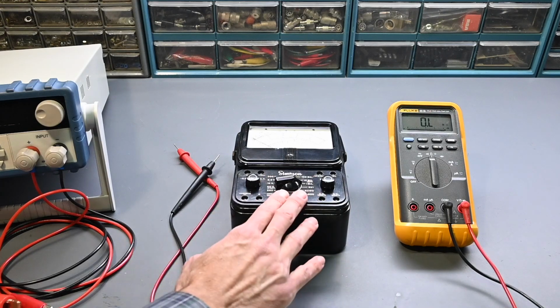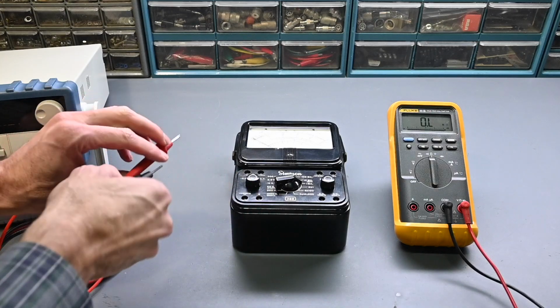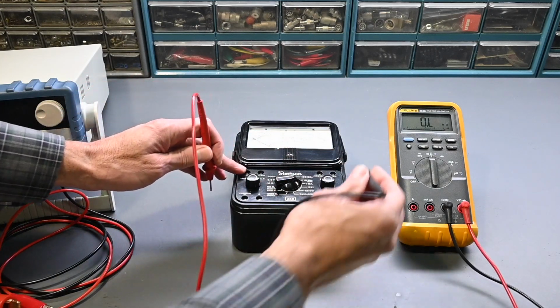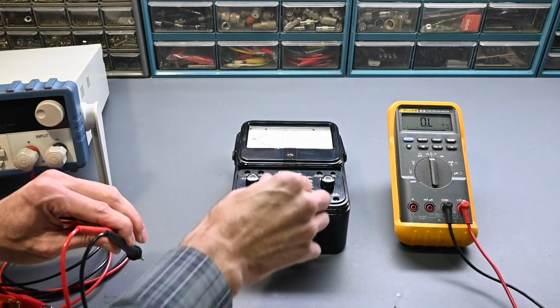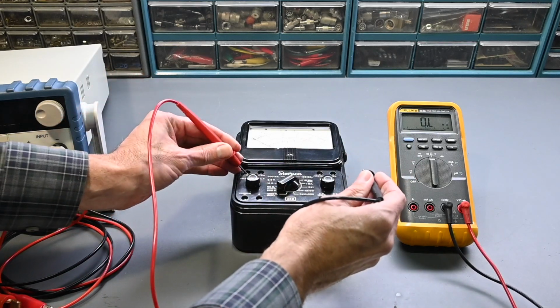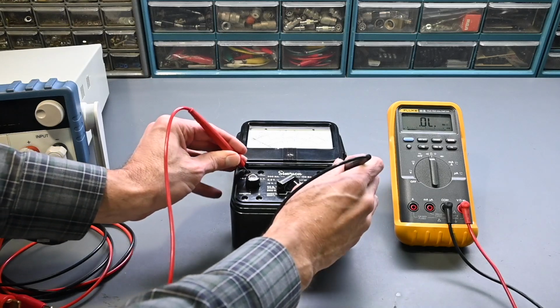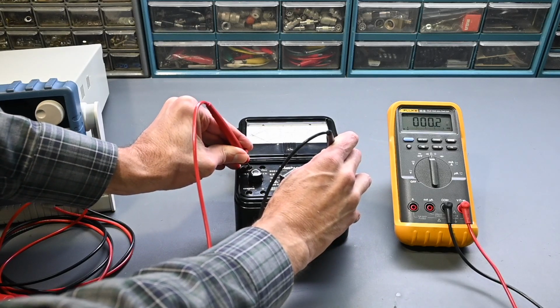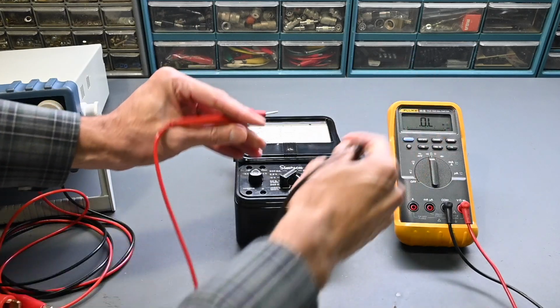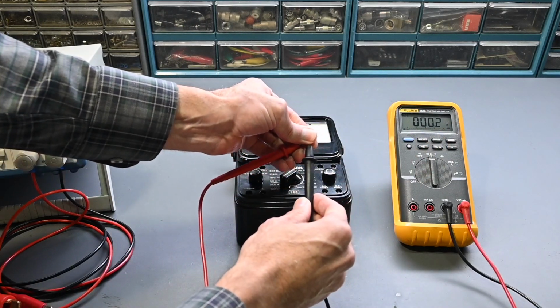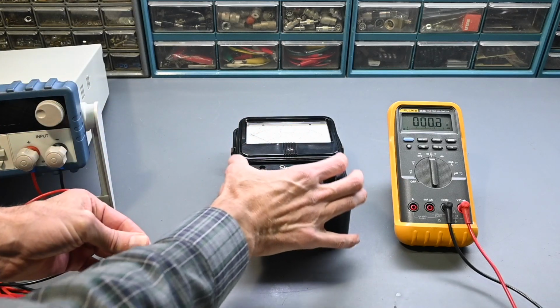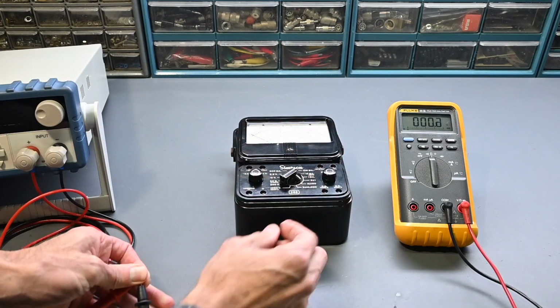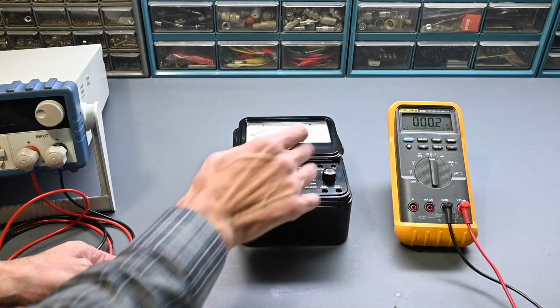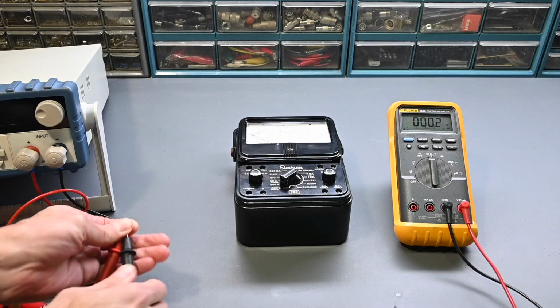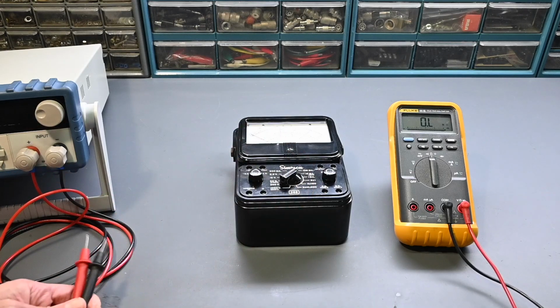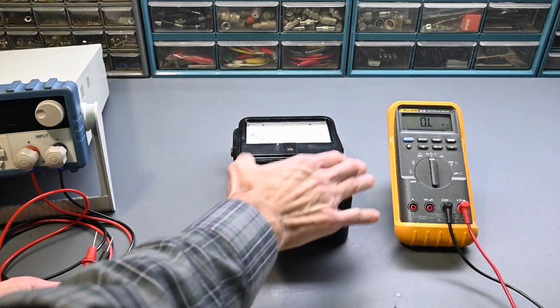And the Simpson 260 does have the ability to measure 10 amps. The 10 amp setting is actually from this jack right here over to this jack right there. I believe it's supposed to be in that position right there, although it shouldn't really make a difference for this measurement. But if I go across those two jacks, you can see the resistance is extremely low. In fact, it says 0.2 ohms right there, which basically looks the same as if I just touched these probes together. So really, this shunt that's in here on the 10 amp setting is extremely low value. It basically looks like just a heavy gauge piece of wire between the two jacks, but it is a very precision resistance, just a fraction of an ohm. So you'd have to have a different meter to even read that value.